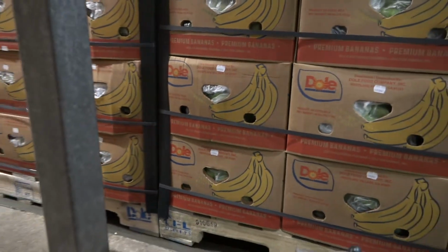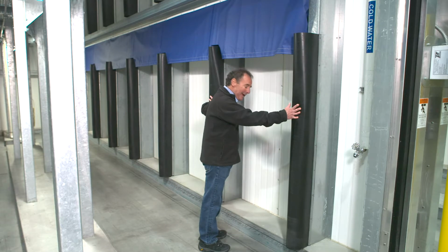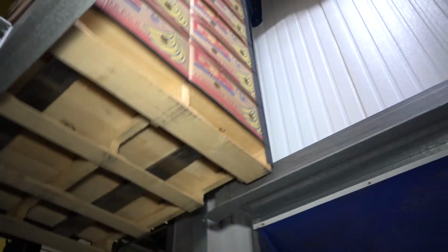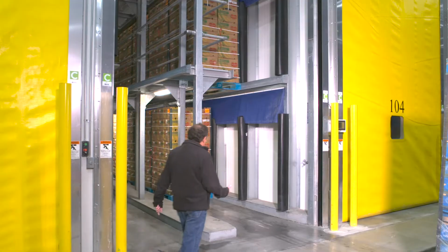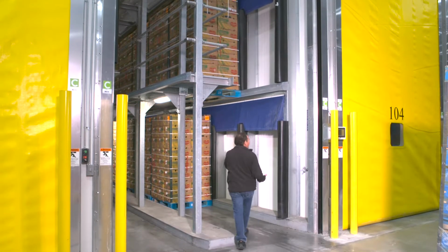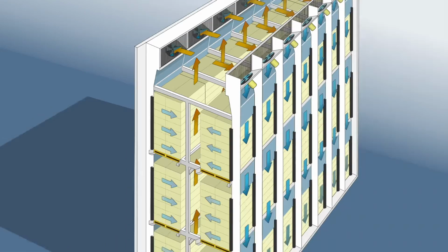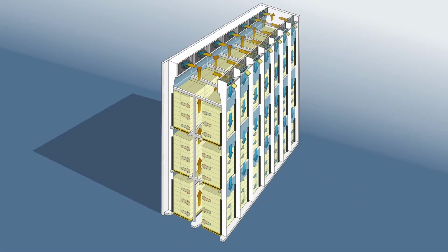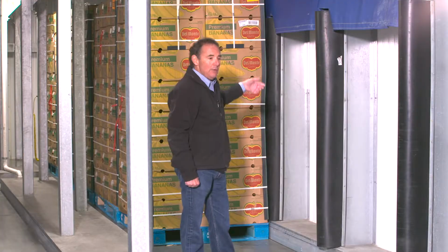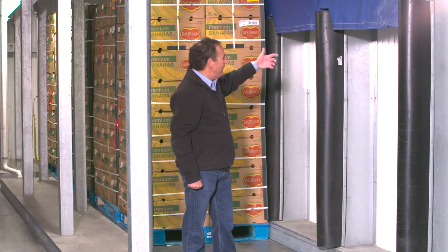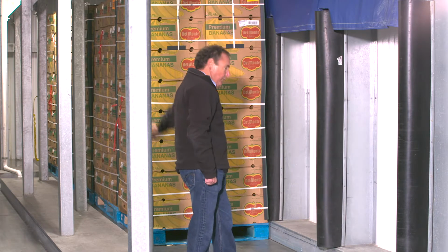Proper pallet positioning is critical to the performance of the ripening room. Pallets need to be tied up against bulb gaskets and tied up against a curb and pallet rails in order for the room to perform properly. A pallet must be loaded into each pallet position below the forced air fan. If any pallet position is left open, you won't have proper air circulation. And the air is going to bypass those pallets and follow the path of least resistance, flow right out here.